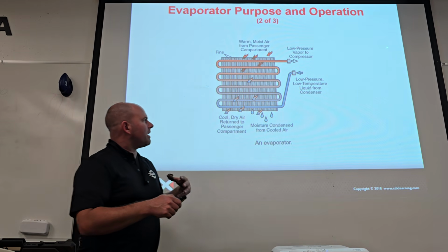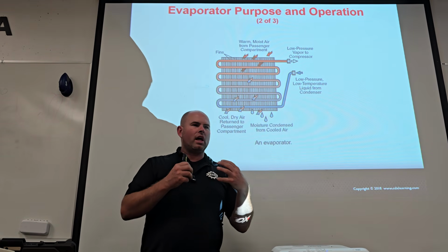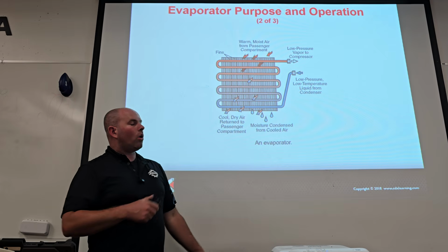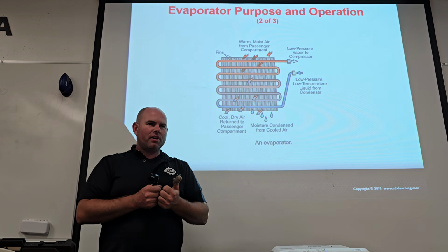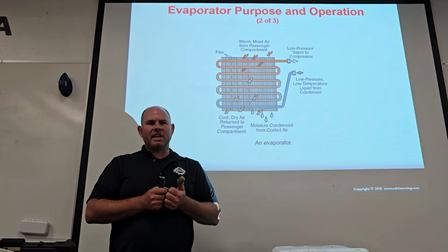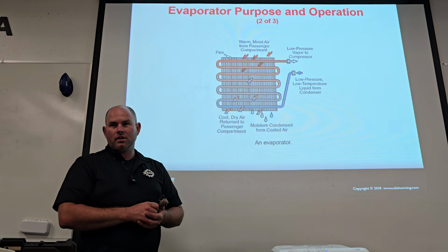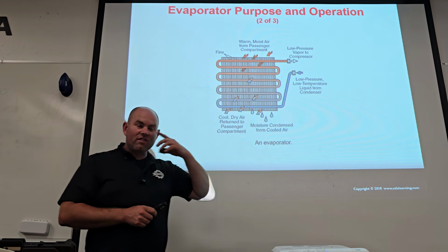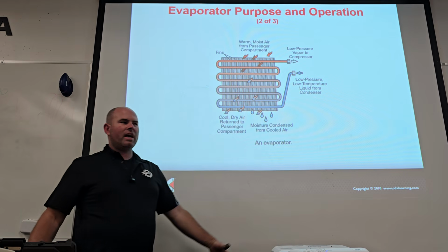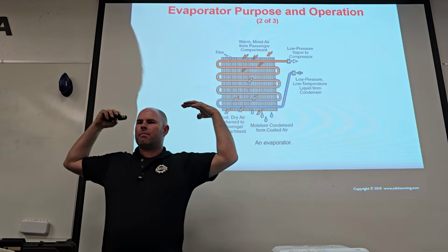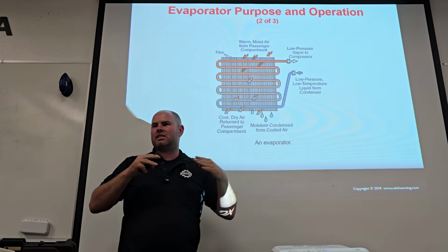So if you think about it, the refrigerant came in, it didn't have a whole lot of heat, a whole lot of BTUs in it, it left with a whole big old bundle of BTUs. Why does it not feel hotter? Because it was latent. It came in as a liquid, it left as a gas. Make sense? It's kind of crazy. So if only you could visualize it, you'd be like, yeah, the refrigerant strolled into that evaporator and it picked up a whole bunch of heat. Now it's carrying it, but you can't see it because the heat's hidden. It's latent.